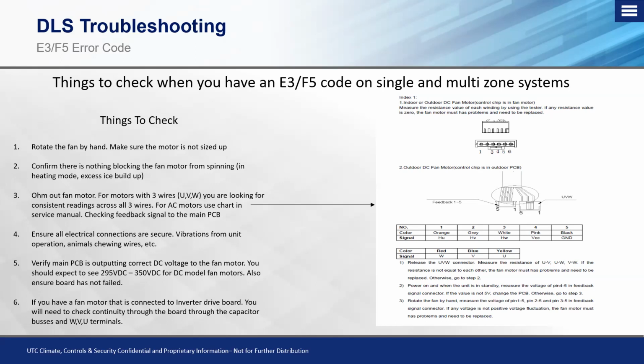Now, of course, if you're not getting that, you guys know what to do if you're getting a voltage reading that's less, or you're not seeing a voltage reading that's within that range. Of course, you always want to confirm your incoming AC power first. Okay. Another thing you want to verify on there too, I've seen it happen before, even with surge protectors on there, where you have an issue where an outdoor board has failed.